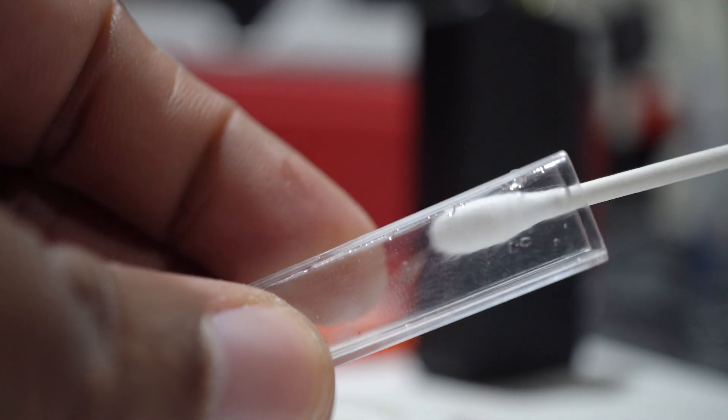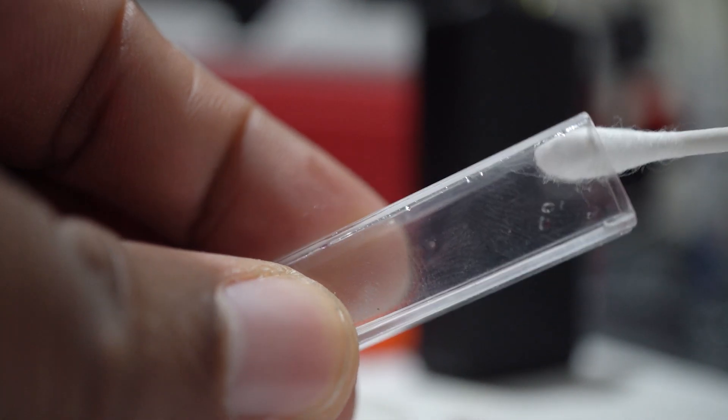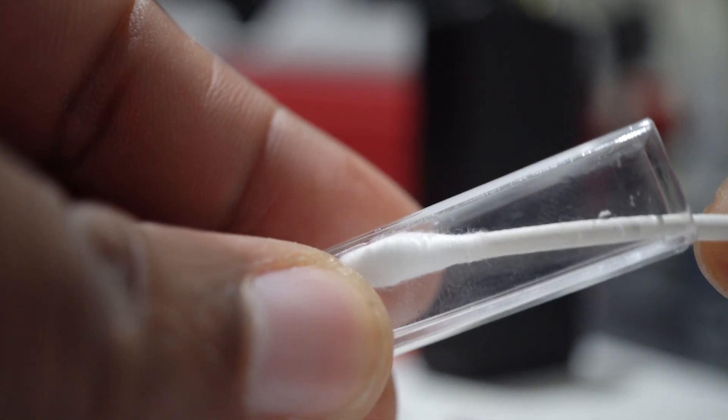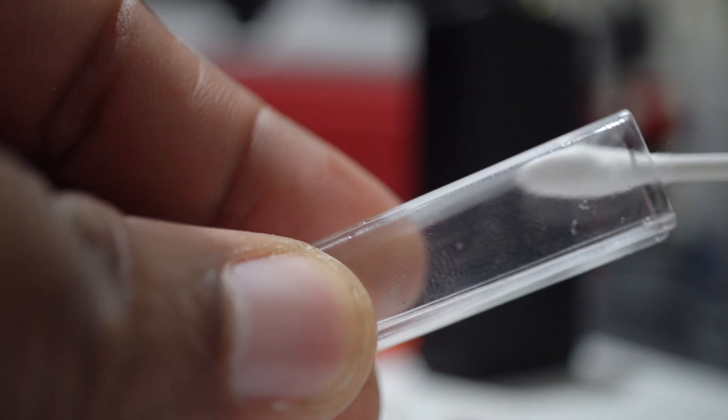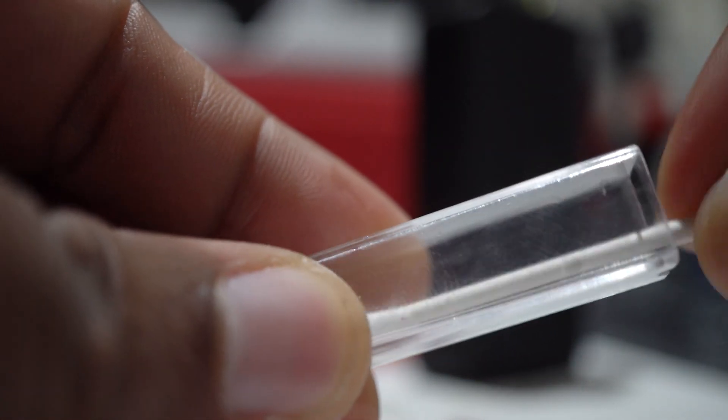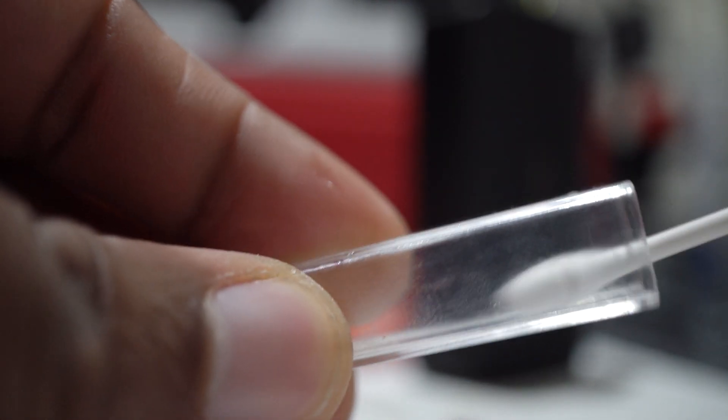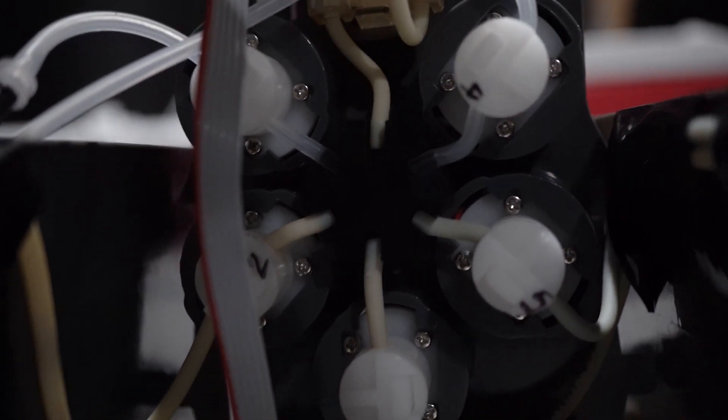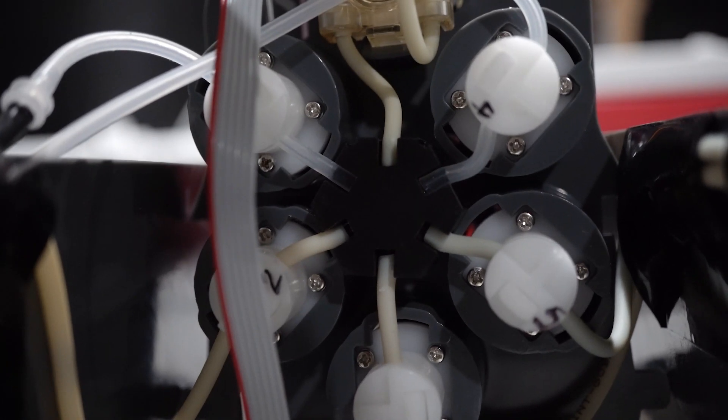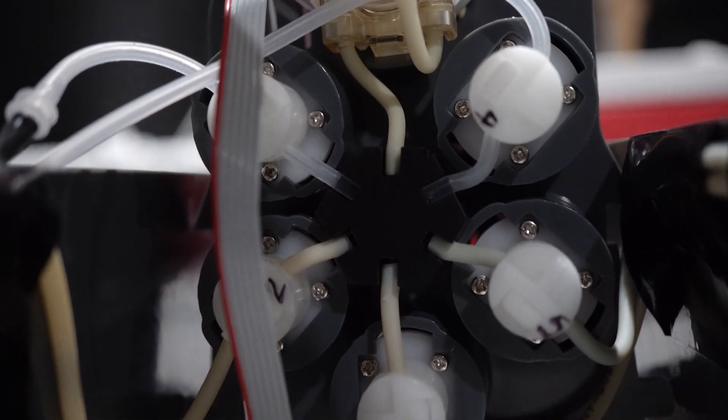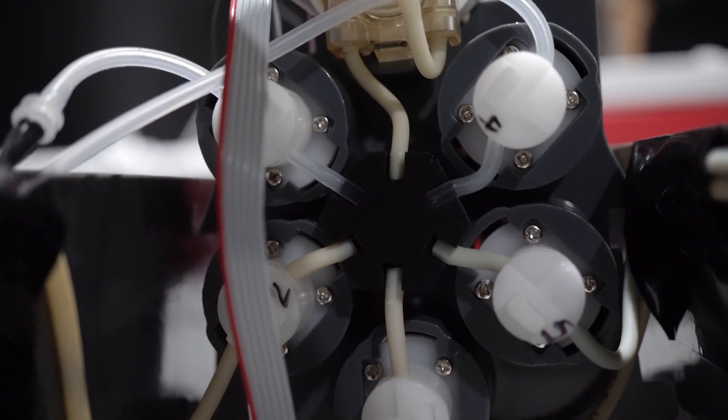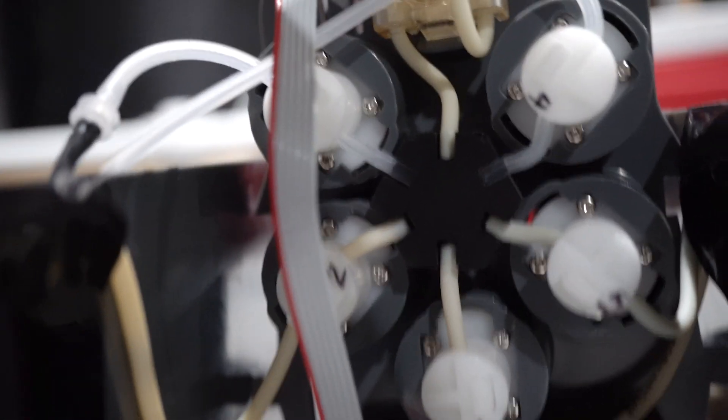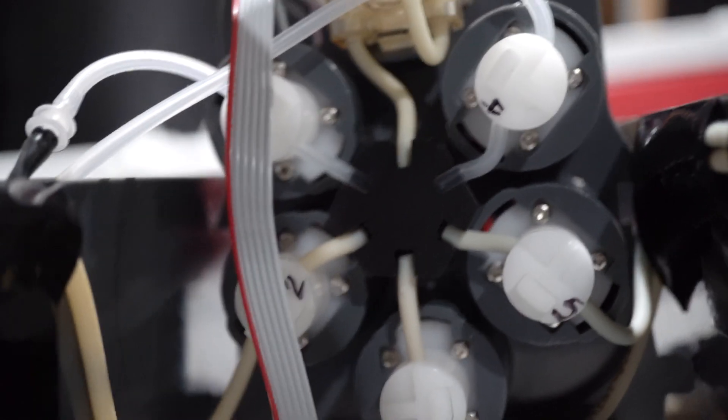Now you've cleaned your chamber. Now the thing about it is that at this point your repairs and maintenance are technically complete. So this is a time for you to go over each connection, especially the tubes, to make sure that everything is seated well and in its correct position. Make sure that the micro dosing pumps heads are seated in the dosing heads. So that means you make sure that tube is all the way into that dosing head, and they just slide and clip in. So there's no crazy unscrewing or anything like that. They just clip right in.